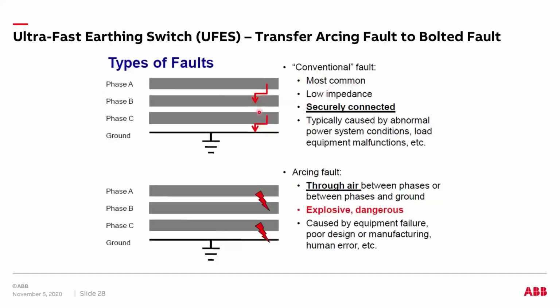So you have a conventional fault, which is typically a low impedance fault, right? Whereas if you have an arcing fault, it is between air, and it can be explosive and can cause significant damage to the equipment as well as to the operator, depending upon the type of the equipment, right? So we are converting this kind of fault into a conventional three-phase to ground fault, which creates a low impedance path for the fault, and that can be effectively interrupted by your 50/51 relay, and can be eliminated or isolated in a safe manner, right?